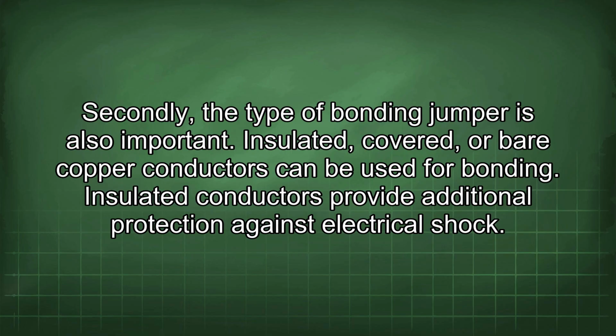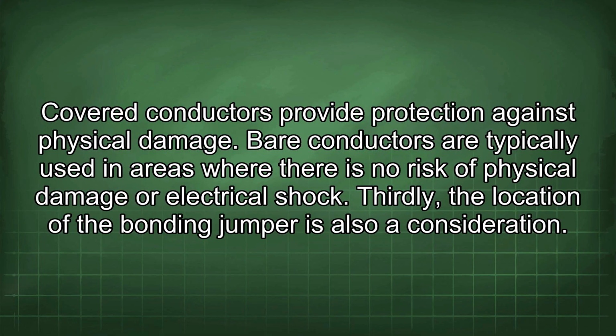Secondly, the type of bonding jumper is also important. Insulated, covered, or bare copper conductors can be used for bonding. Insulated conductors provide additional protection against electrical shock. Covered conductors provide protection against physical damage. Bare conductors are typically used in areas where there is no risk of physical damage or electrical shock.